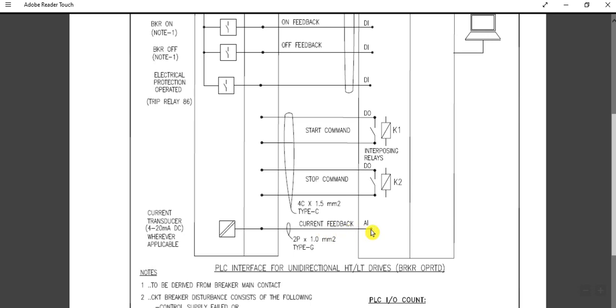Another signal is the current feedback — AI, analog input. A current transducer is located inside the switchgear, and it provides a 4 to 20 milliamp DC signal. This analog signal representing the current is transferred to the DCS or PLC cabinet for indication purposes. For this we have used a 2-pair, 1 square mm cable.